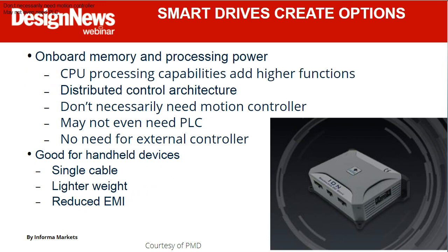Another integration approach is the whole smart drive phenomenon, and it's been going on for a while, but it really shines in this medical space because you've got a drive with onboard memory and processing power, and all of a sudden you've got the ability to not have a separate controller in addition to the motor and the drive.